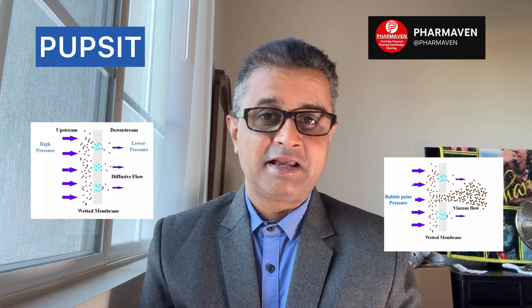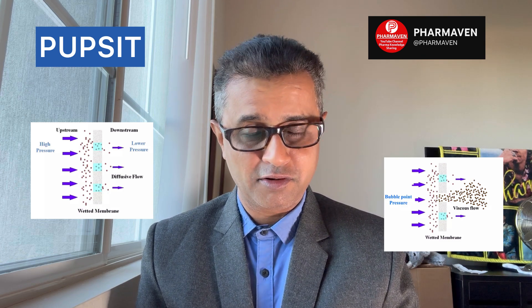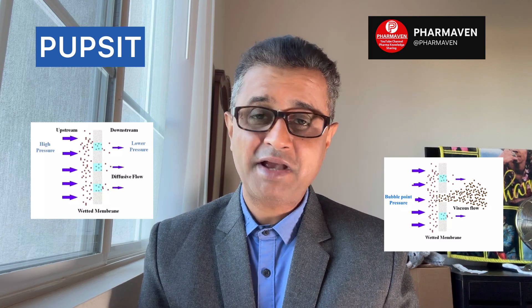Any flaw or damage in the filter can be detected. It must be detected prior to use because once we use the filter for filtration, any minor damage, minor leak, or minor pore can be blocked by particles from the product — blocked if the product is viscous, or blocked for other reasons — and the damage can be masked. Because of this masking effect, a filter that was non-integral and had damage prior to use may actually pass the post-usage integrity test.